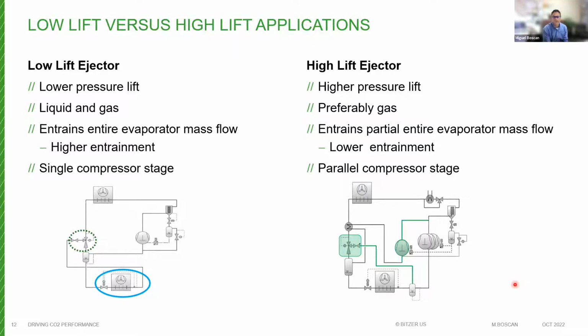And it could be a good solution if you have control issues on a rack with unloading, or inability to really control or meet the part load capacity you need, and also an opportunity to increase system efficiency on a rack that is already existing at a relatively low investment.